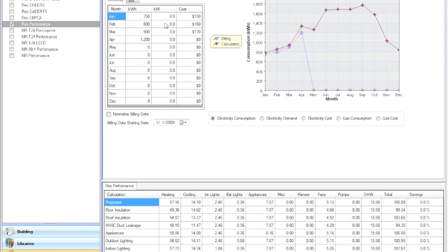The reason you want to use a standardized year is if you use one specific year as the basis of the calculation, this year being a great example, your cooling energy usage is going to be significantly underpredicted for future years. So if we look at this summer, everything's been cool, people haven't been running the air conditioning, etc. It would be a very bad thing to base your future predictions on energy savings for the homeowner. So right away, you can jump in and look at weather patterns as being one possible explanation for that.